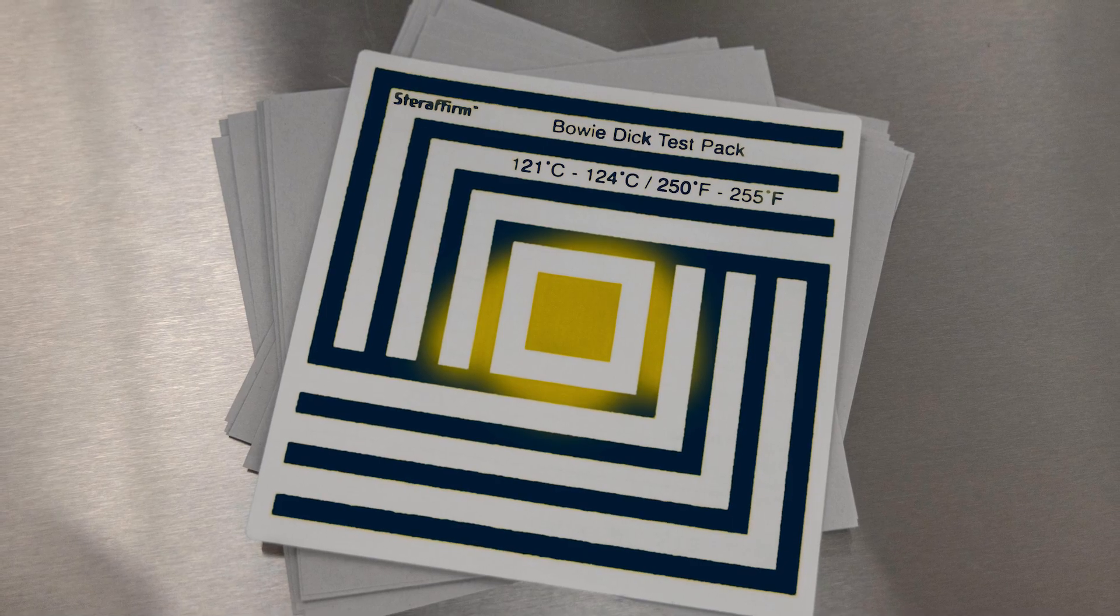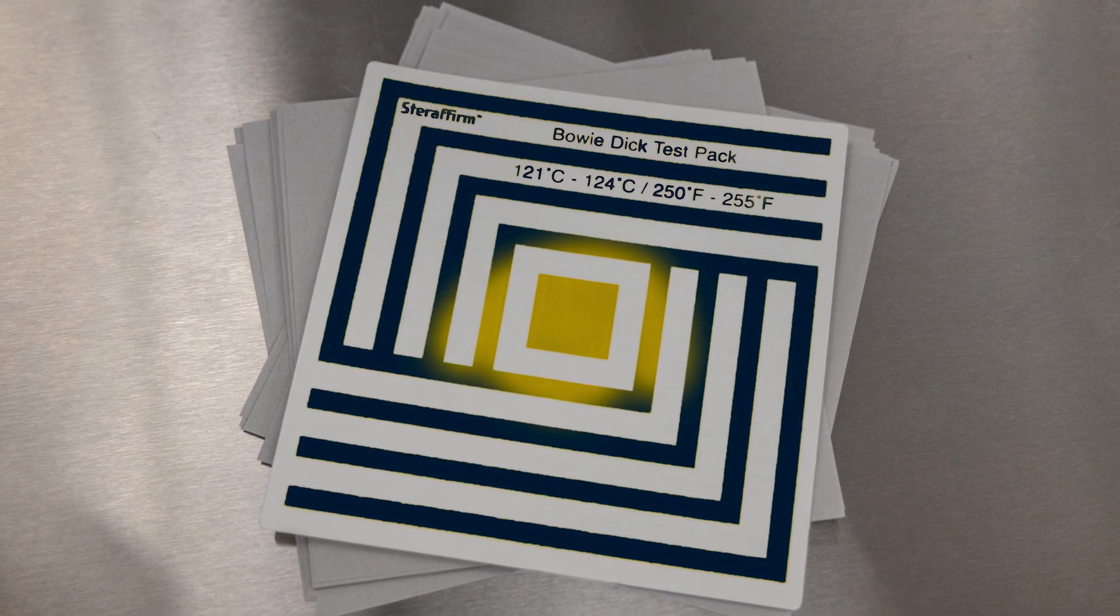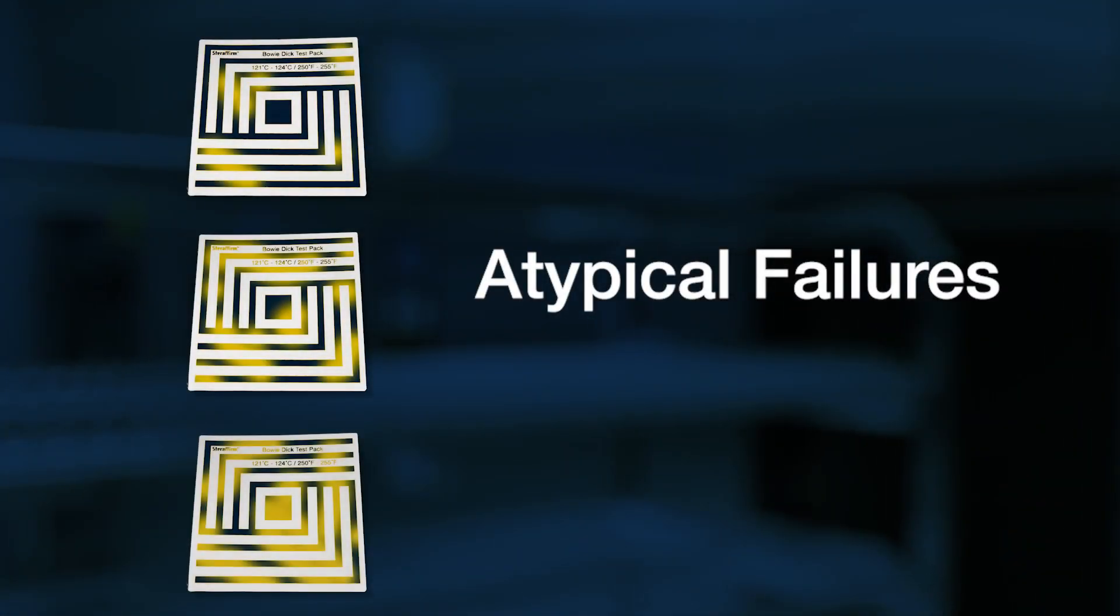A typical failure, such as residual air in the chamber, shows a concentration of yellow towards the center of the carton.